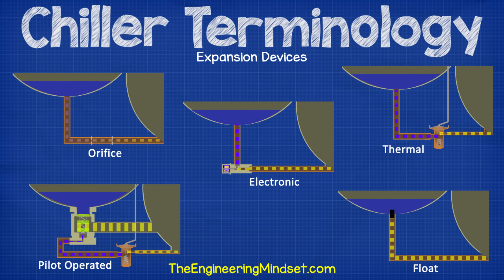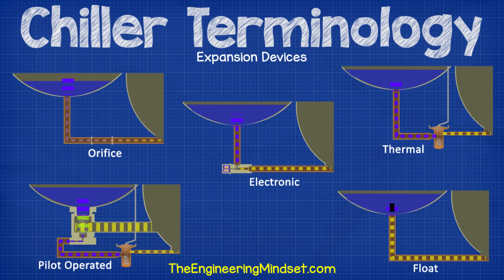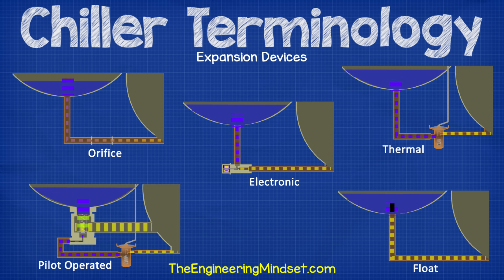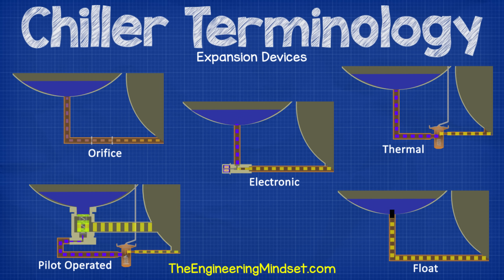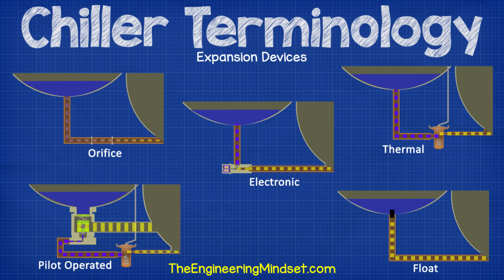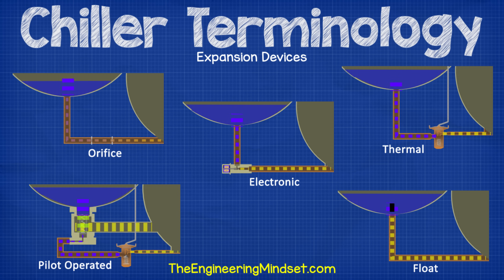Expansion valve or device. This is a device used between the condenser and the evaporator. These cause a pressure reduction in the refrigerant as well as controlling the amount of refrigerant entering the evaporator, which is used to control the superheat. There are many different types used in chillers. Some examples of chiller expansion valves and devices are orifice plate, float valves, thermal expansion valves, electronic expansion valves, as well as pilot operated thermal expansion valves.